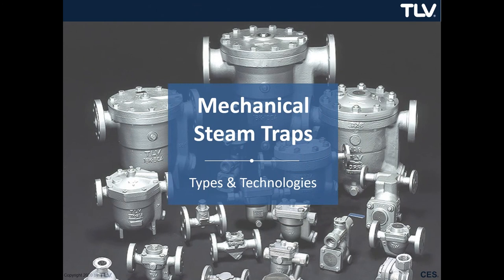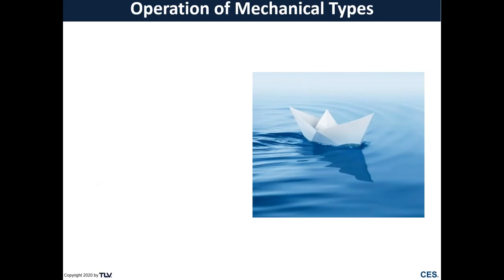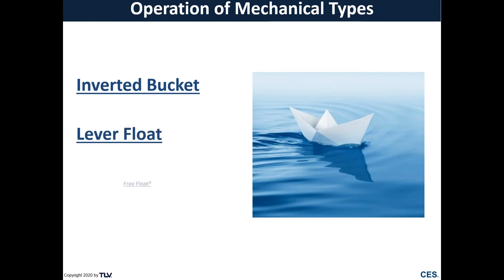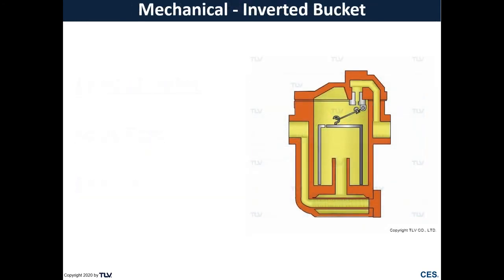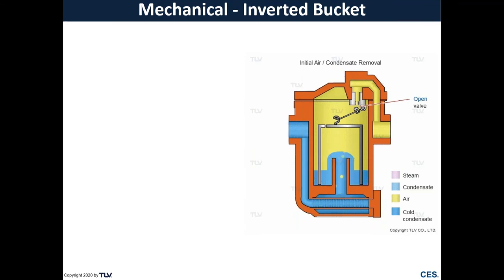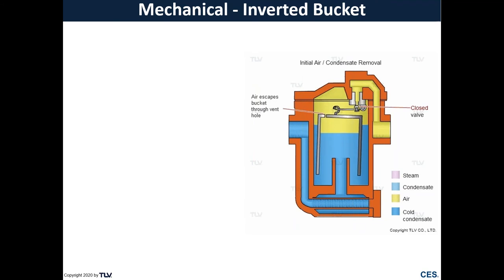The next trap I'd like to cover is mechanical steam traps. The operating principle for mechanical steam traps is buoyancy. So we're going to cover an inverted bucket trap, a lever trap, as well as TLV's free float. So here's an animation of an inverted bucket trap. You can see the buoyancy element is that bucket since it's upside down. So this bucket's not going to have buoyancy until we build up a water prime and there's either steam or air inside of that bucket, which is then going to lift the bucket, closing off your valve seat. And you can see those linkages with your valve head and valve seat on the top side of that trap.